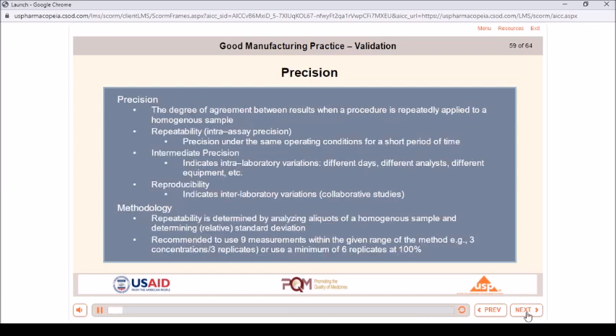Precision: the degree of agreement between results when a procedure is repeatedly applied to a homogeneous sample. Repeatability, or intra-assay precision, is precision under the same operating conditions for a short period of time. Intermediate precision indicates intra-laboratory variations: different days, different analysts, different equipment, etc. Reproducibility indicates interlaboratory variations, collaborative studies.